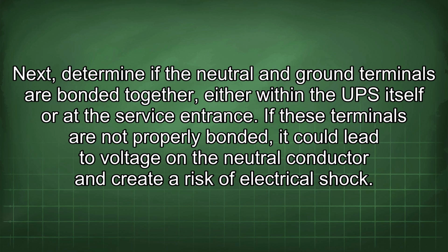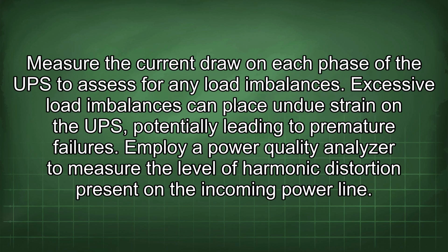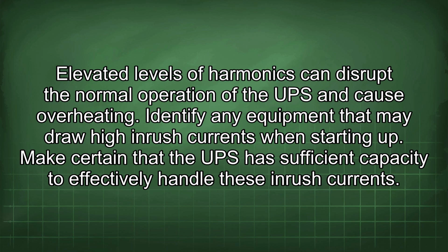entrance. If these terminals are not properly bonded, it could lead to voltage on the neutral conductor and create a risk of electrical shock. Measure the current draw on each phase of the UPS to assess for any load imbalances. Excessive load imbalances can place undue strain on the UPS, potentially leading to premature failures. Employ a power quality analyzer to measure the level of harmonic distortion present in the incoming power line. Elevated levels of harmonics can disrupt the normal operation of the UPS and cause overheating.